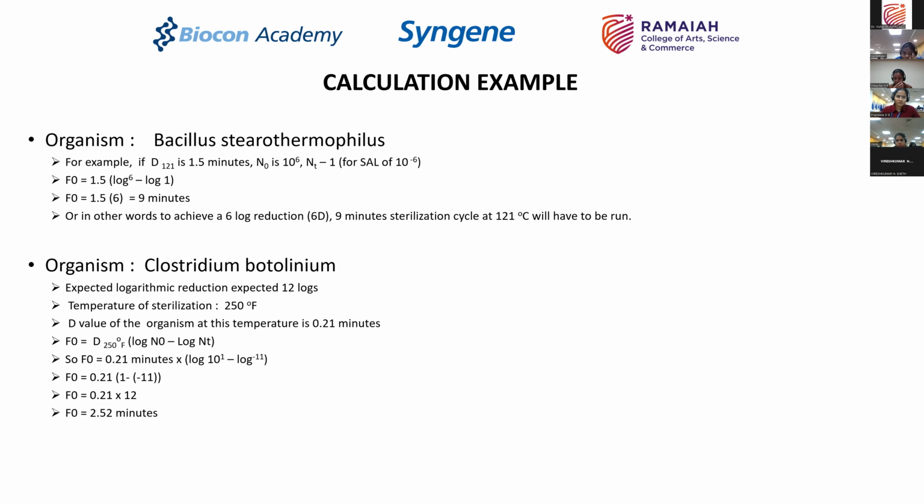So what you will do is, when you put it on a given load, you know that I had a biological indicator with 10 to the power of 12 spores already on that indicator. The indicators are actually spiked indicators where they have a certain quantum of Bacillus stearothermophilus on that strip.